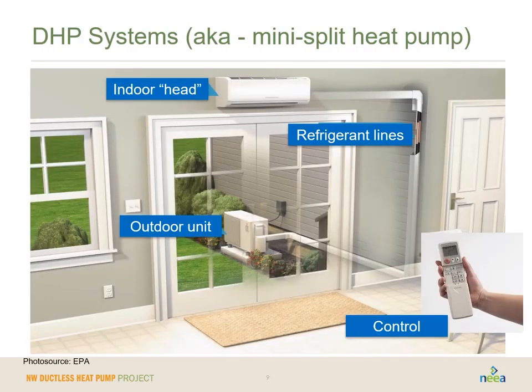So let's keep going with the basics. A DHP system, or a ductless heat pump system, also referred to as a mini split heat pump. And the reason why it's a mini split is if you notice the size of the compressor, the outdoor unit here, it's about a third to a quarter of the size of an old compressor for a standard air conditioner or a central heat pump. Hence the term mini split.